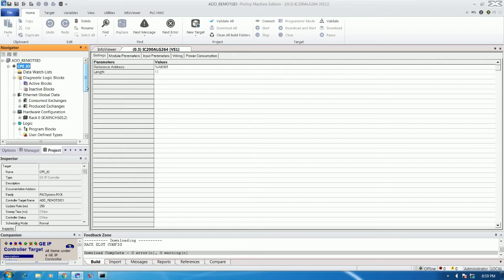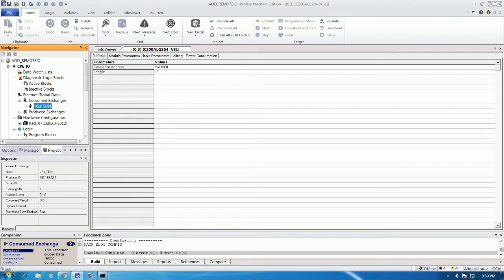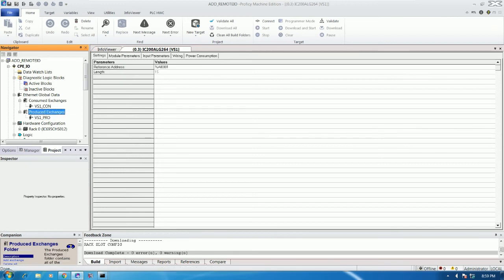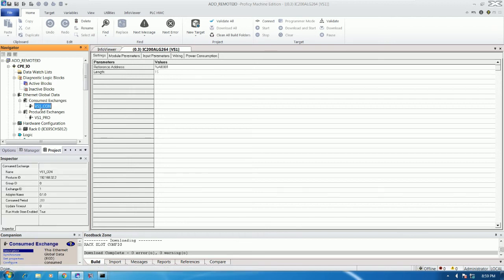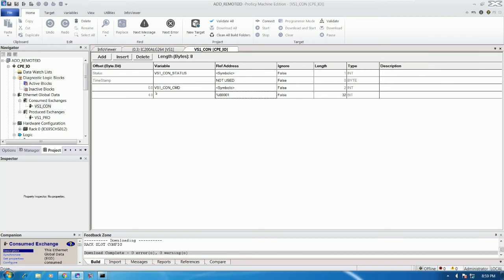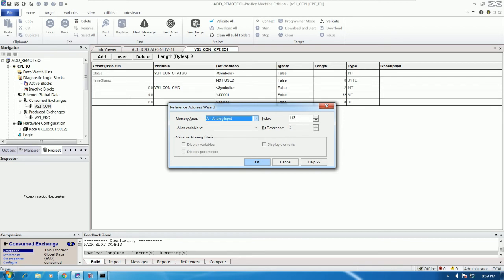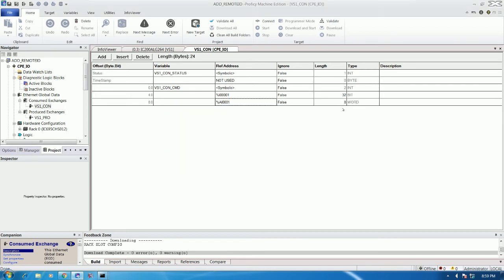Now we need to configure the consume block, because we are using analog input. For analog input or digital input, we must add a consume entry; for analog output or digital output, we add a produce entry. Produce means sending data to another device; consume means receiving data from another device. Right-click on the consume section, add one more for analog input. Go to the AI tab and it will start from address 1 — 50 bytes total, meaning 50 channels.